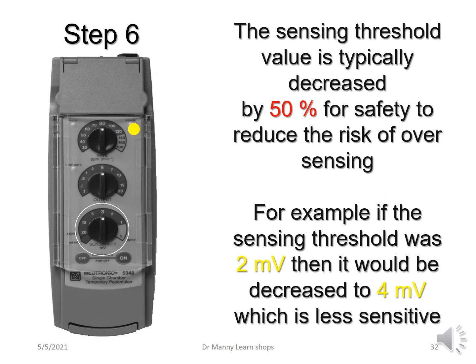In step six, the sensing threshold value is typically decreased by 50% for safety to reduce the risk of over-sensing. Remember, the pacemaker is just a machine and depends on you to set it correctly. For example, if the sensing threshold was two millivolts, it would be decreased to four millivolts — the figure increases but you are actually decreasing sensitivity. Two millivolts is more sensitive than four millivolts; it has been adjusted to four millivolts, which is less sensitive, to prevent over-sensing.